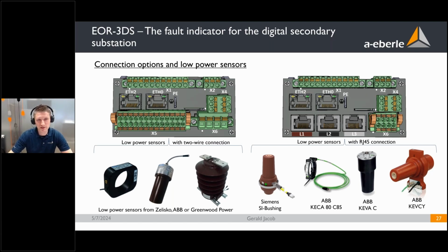Sometimes you only want to measure 3 phases, 3 voltage and 3 current phases, but you can also measure the 0 sequence voltage and the I0 directly with a CBCT if you want to. What else can we see? Besides the X5, on the X5 there are also 4 binary inputs on this terminal plug. Then X6, we also have 2 additional binary inputs that are not only up to 60 volts, but up to 132 volts. Then we have X4, which is the terminal for RS485 for serial protocols, serial interface.